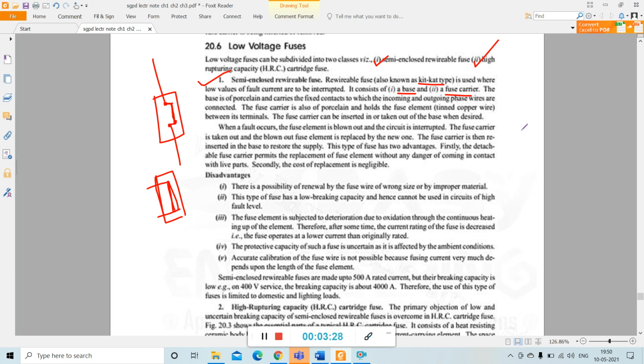So this type of fuse has two advantages. What are those? Firstly, the detachable fuse carrier permits the replacement of the fuse element without any danger of coming in contact with live parts. That means when we repair the fuse element, there is no danger of coming in contact with live parts. And the second advantage is that the cost of replacement is negligible. Then, what are the disadvantages of this semi-enclosed rewirable fuse? There is a possibility of renewal by fuse wire of wrong size or by improper material. That means when we repair the fuse element, we may use a wrong size fuse wire, or it can be of improper material.